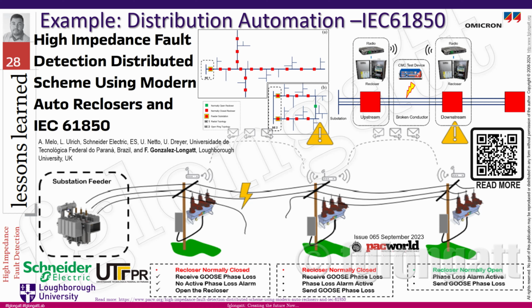We use IEC 61850.8.1, in other words the GOOSE protocol, to detect and isolate the broken conductor. When the fault occurs, you can see that one of the reclosers is indicating that the voltage in one of the lines is zero, and the other one is indicating the same. So there is a current interruption and also a voltage difference between the terminals. The reclosers take the signal, generate a GOOSE message, and communicate using the GOOSE protocol. This was one of the publications.